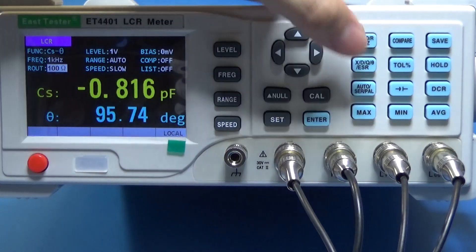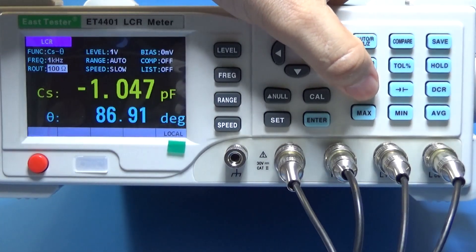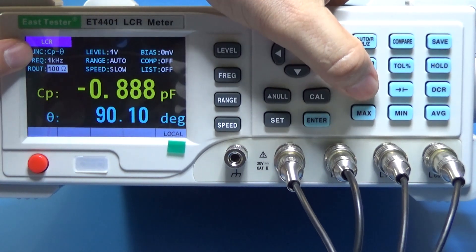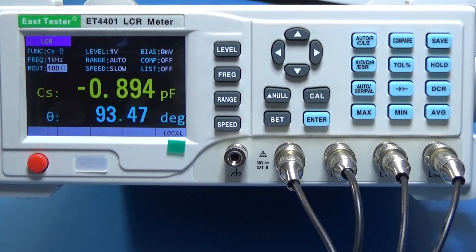A bridge meter is not like the capacitor meter. This device makes a kind of bridge and what it does is it changes the value of the other impedance to match the one we are doing the measurement. So in that case, the bridge has the capability to work either in serial or parallel, and the system has the button of auto to try to detect it. S for serial, P for parallel.